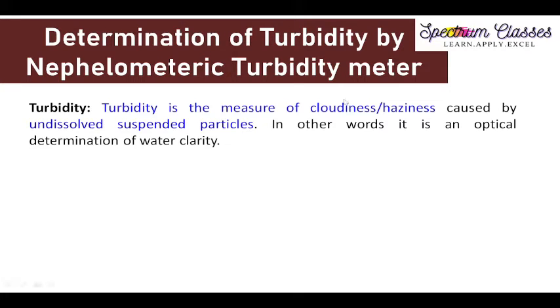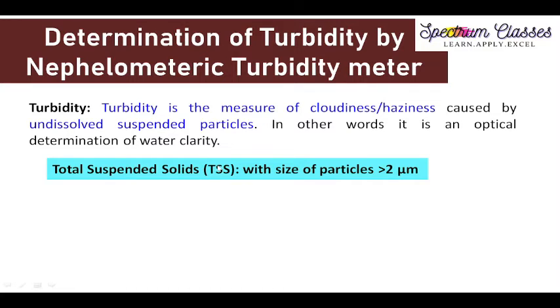First, we are going to understand what is called turbidity. Turbidity is the measure of cloudiness or haziness caused by undissolved suspended particles. In other words, it is an optical determination of water clarity. Now, what causes this turbidity? Total suspended solids — those particles which have a bigger size, greater than 2 microns — are considered suspended particles. Through turbidity measurement, we are going to measure these total suspended solids.